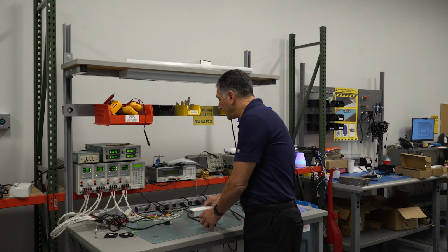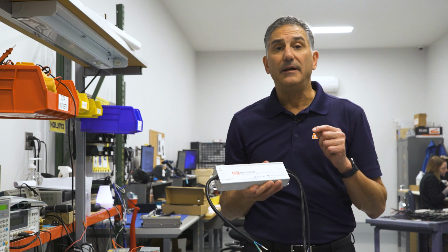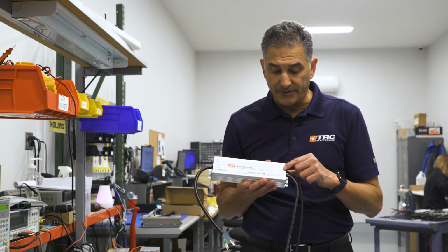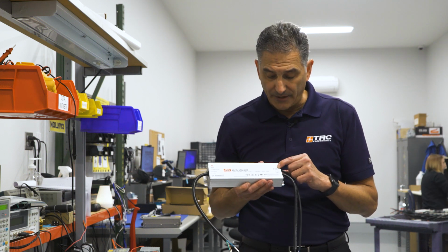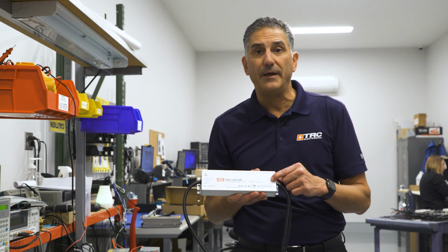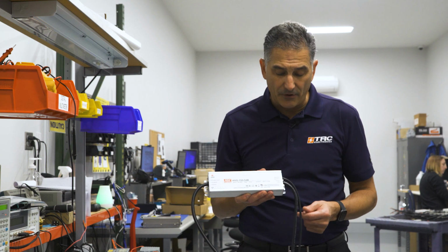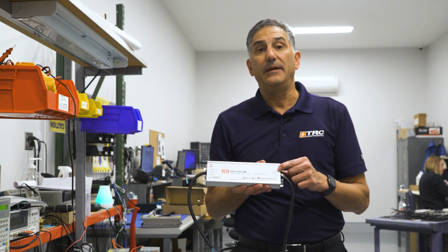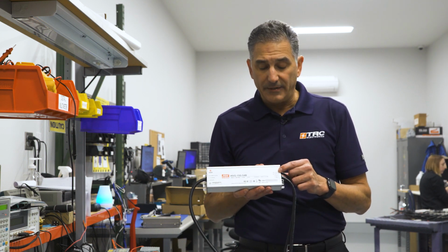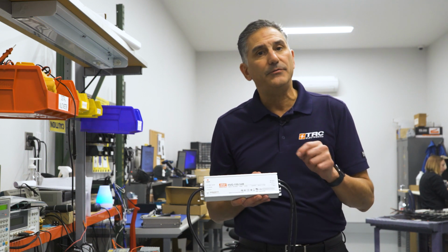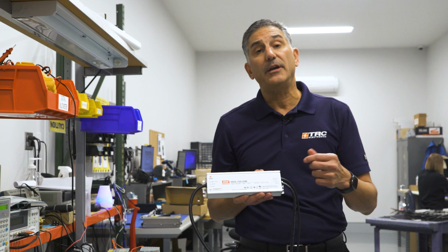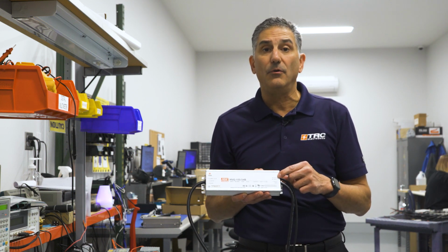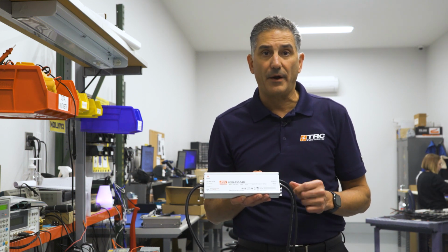Now, if you notice on a dimming driver that has DC dimming, you'll notice that there's an actual set of dimming wires, and you'll see it by a plus dim and a minus dim designation. Now, it also shows the wire colors. These wire colors, however, can change from time to time, so it's important that you check the data sheet and check the most updated data sheet to know what the color codes of those dimming wires are.